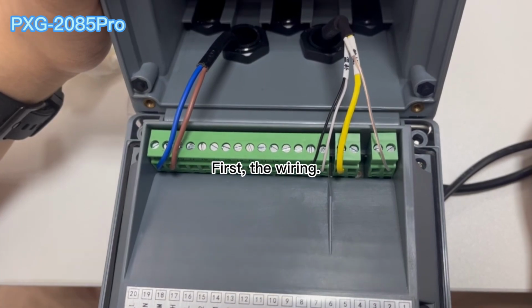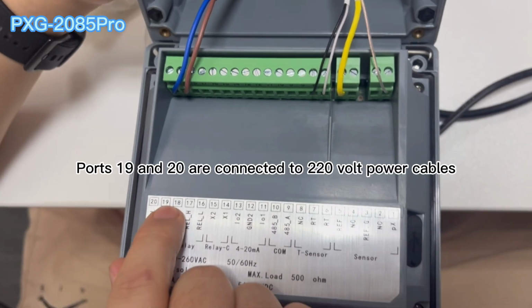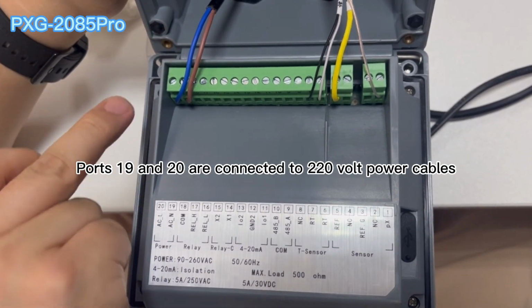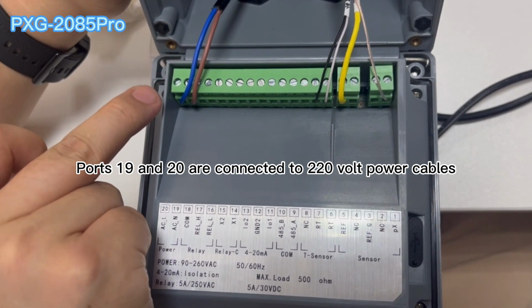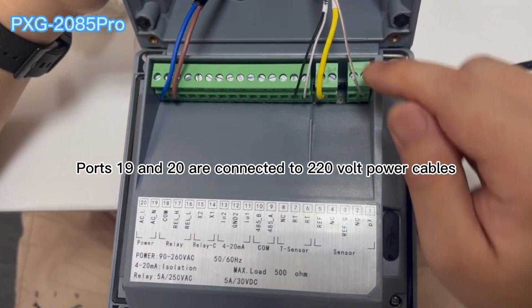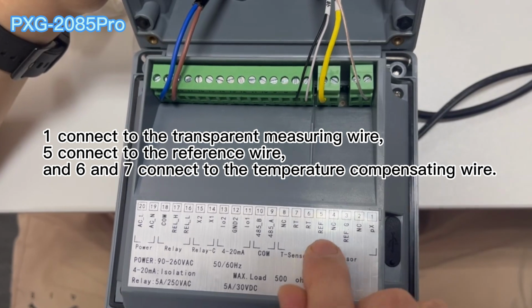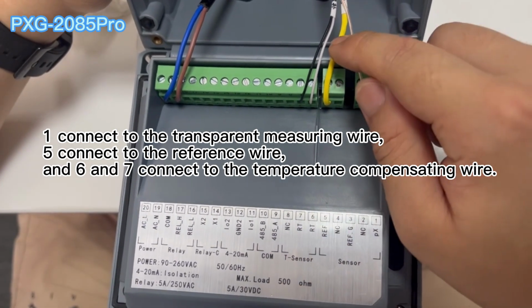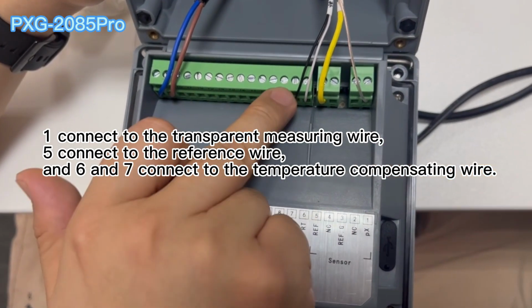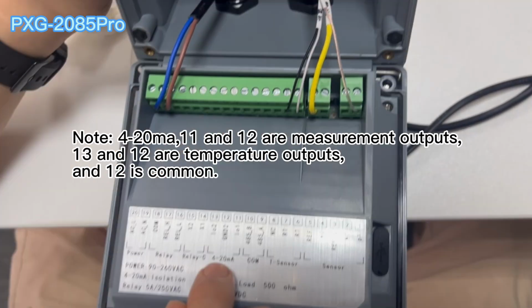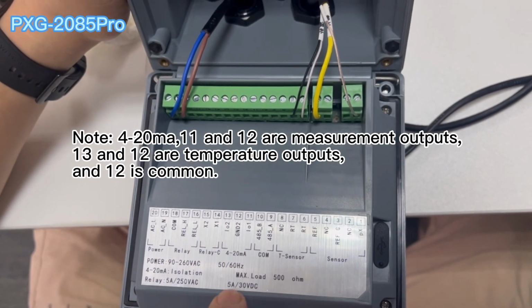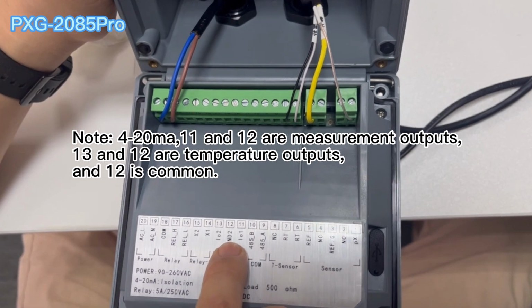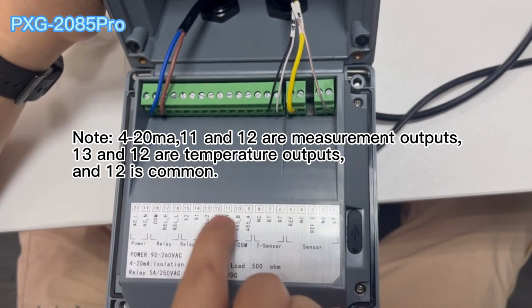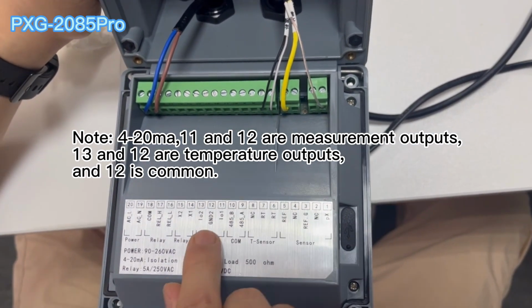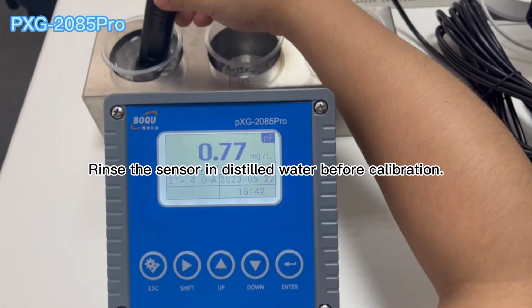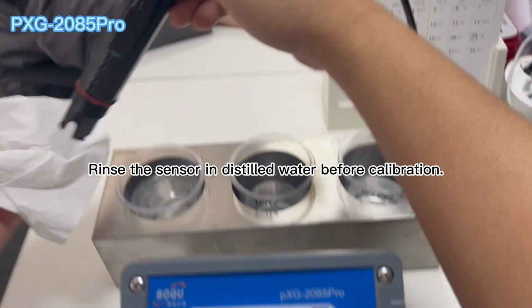First, the wiring. Ports 19 and 20 are connected to 220 volt power cables. 1 connects to the transparent measuring wire, 5 connects to the reference wire, and 6 and 7 connect to the temperature compensating wire. Note, for 4-20mA, 11 and 12 are measurement outputs, 13 and 12 are temperature outputs, and 12 is common. Rinse the sensor in distilled water before calibration.